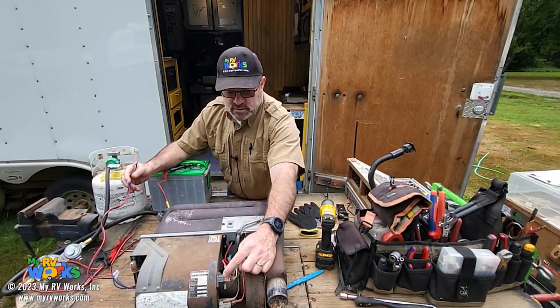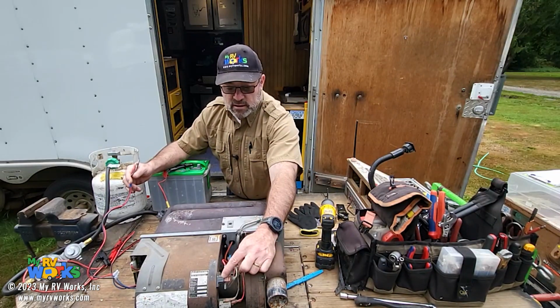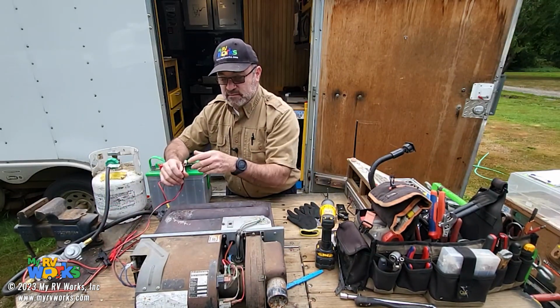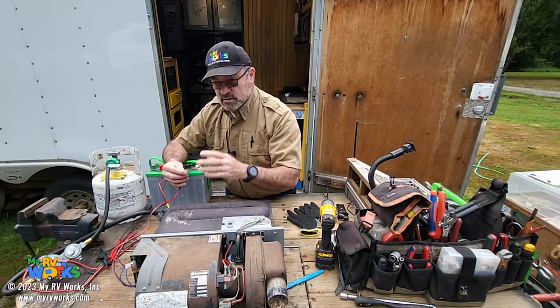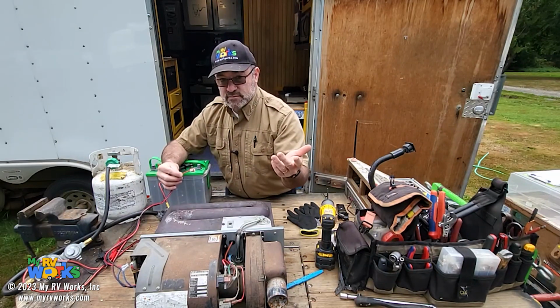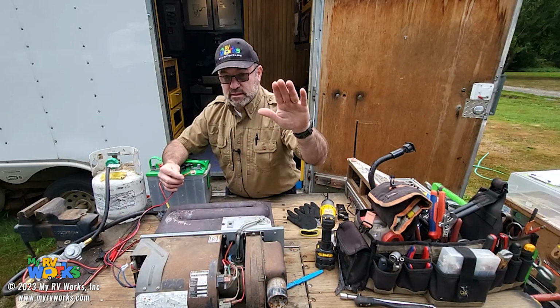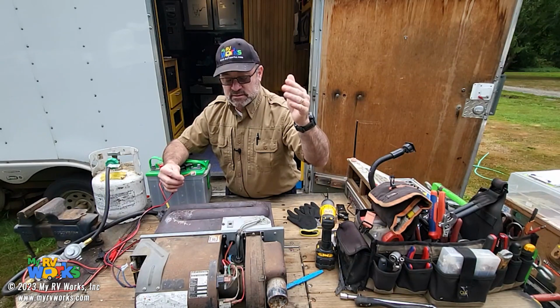Maybe that's a standard in the industry, I don't know, but there are blue wires. Now, this one also has a time delay relay on it, so when I connect these, there will be an interval of time before the furnace starts. So I'm just letting you listen to see if it'll ignite and extinguish, ignite and extinguish.